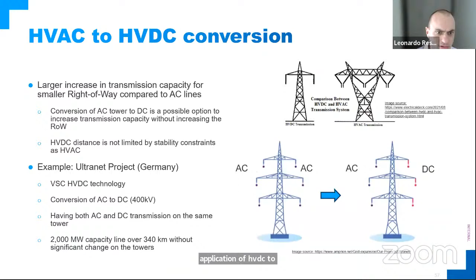That project is a VSC HVDC technology at 400 kV used for a conversion. The line is an existing double circuit AC line, where one of the circuits is now being converted to DC, giving that DC line a 2,000 megawatt capacity. So there's no new right-of-way, just repurposing an existing double circuit AC line into a mixed HVAC/HVDC line on the same right-of-way. As you know, in Europe it's very challenging to build new rights-of-way, so anything we can do to increase transmission capacity without new rights-of-way is very welcome. This is a very interesting application of HVDC to increase grid capacity using the same right-of-way.